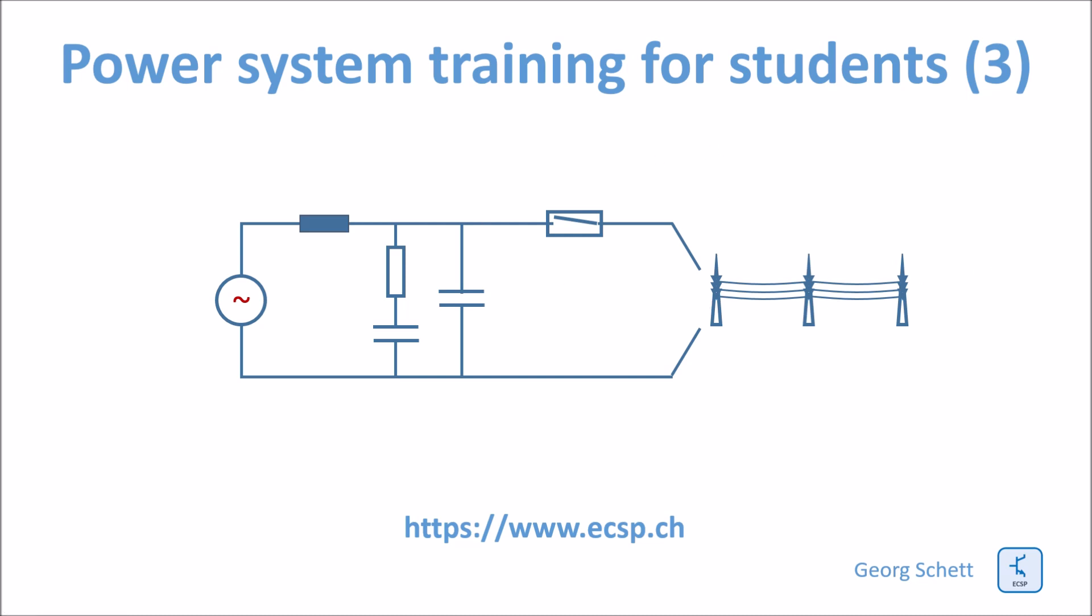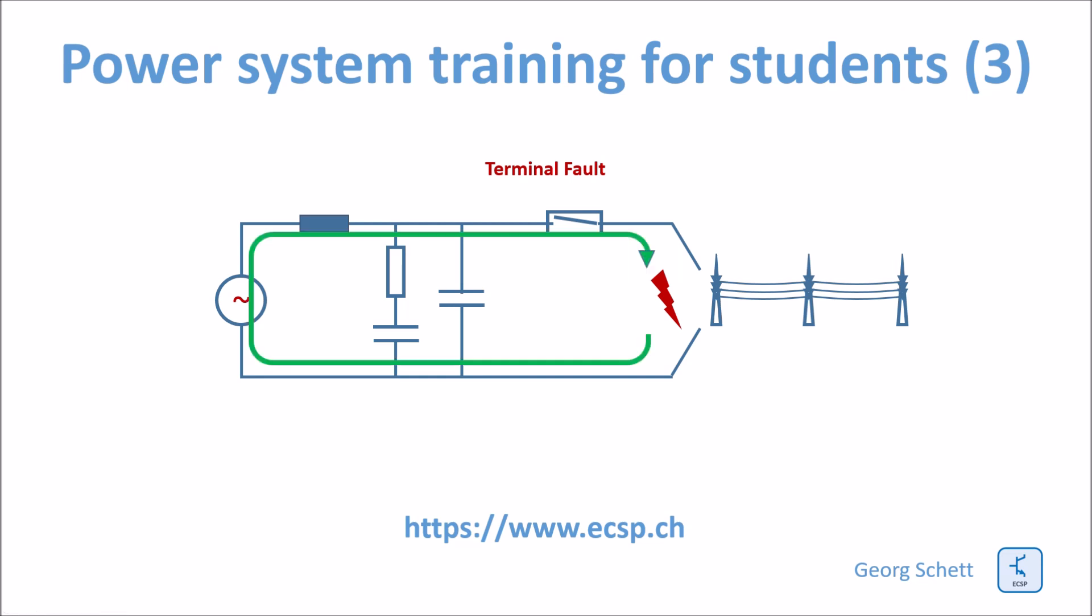In this lesson, we will first look at the terminal fault. The terminal fault is a fault which happens directly at a breaker and normally gives rise to the most severe short circuit fault levels. As soon as there is such a fault, a very high current will flow from the fault location to the source and back. This is a very high short-circuit current.